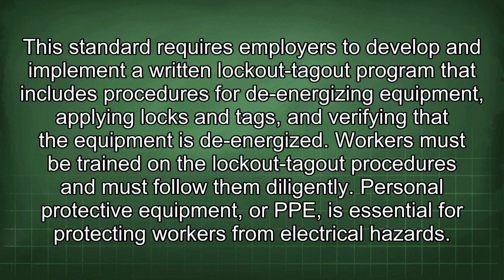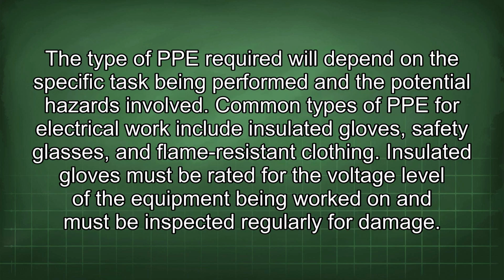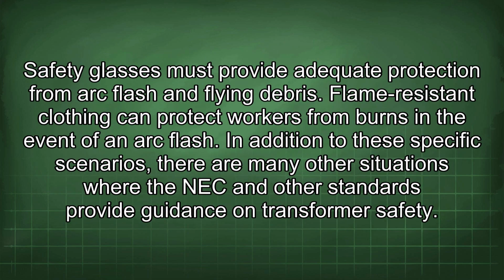Personal protective equipment, or PPE, is essential for protecting workers from electrical hazards. The type of PPE required will depend on the specific task being performed and the potential hazards involved. Common types of PPE for electrical work include insulated gloves, safety glasses, and flame-resistant clothing. Insulated gloves must be rated for the voltage level of the equipment being worked on and must be inspected regularly for damage. Safety glasses must provide adequate protection from arc flash and flying debris. Flame-resistant clothing can protect workers from burns in the event of an arc flash.